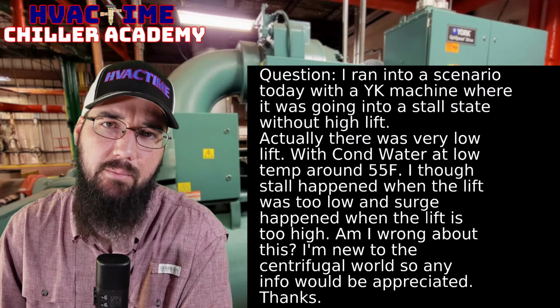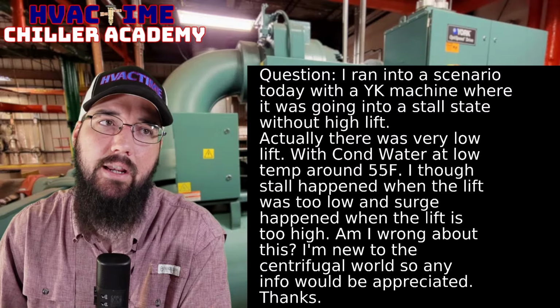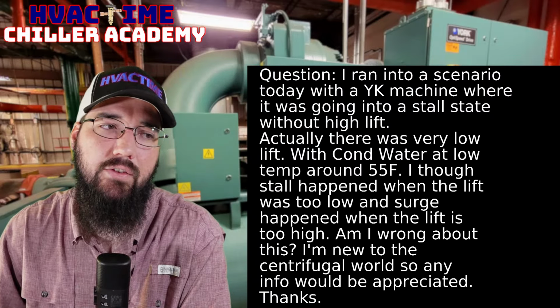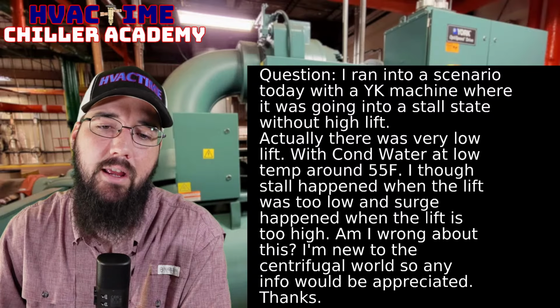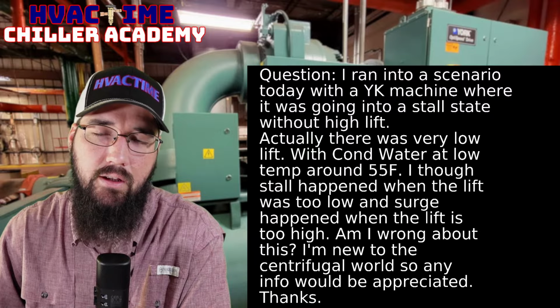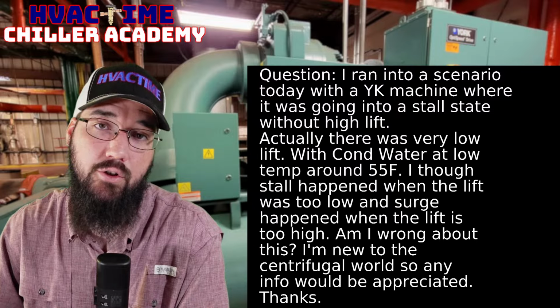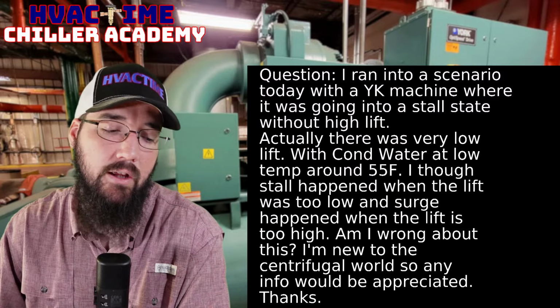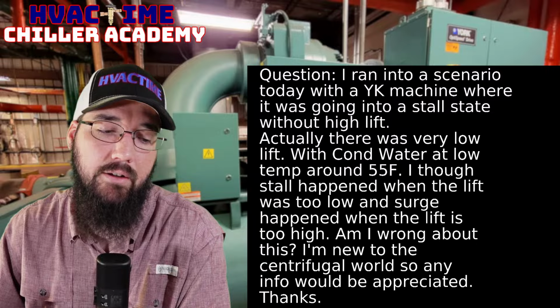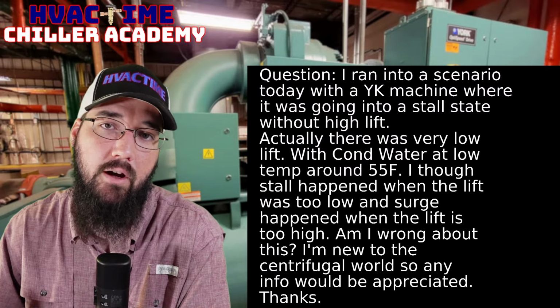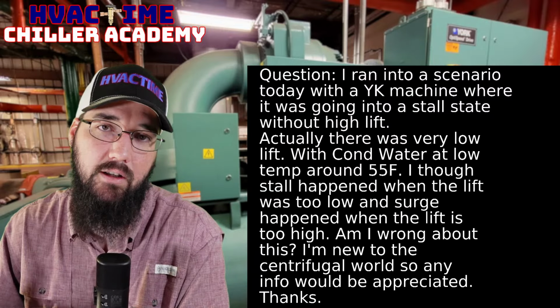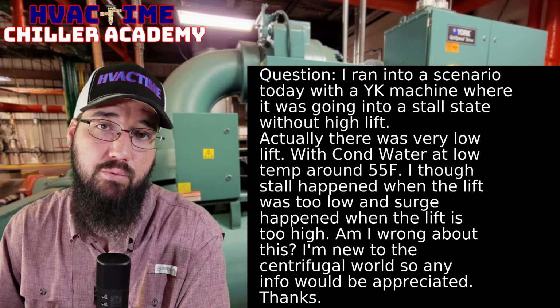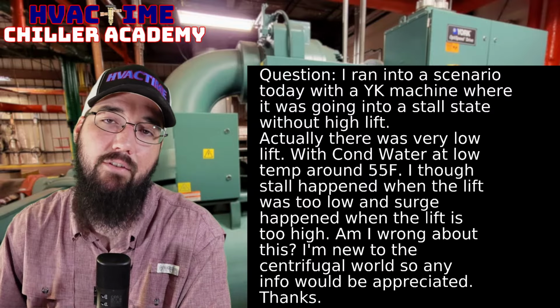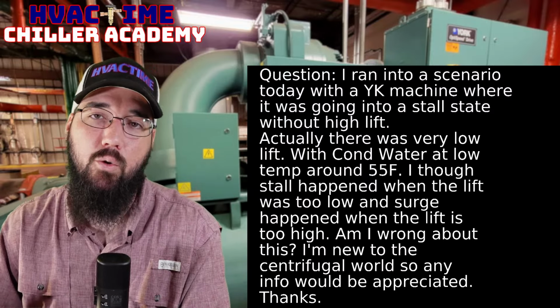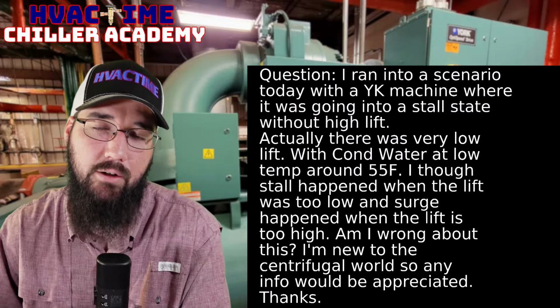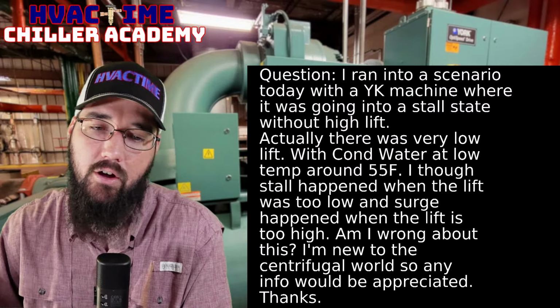But here's something to keep in mind with this. Trane has a similar thing where we have to maintain a minimum lift in order to, one, avoid choke. Now, if you read through Trane's literature, Trane explains that they're more concerned about oil flow control, because if our lift gets too low, it means our differential pressure drops too much, and we start having oil flow or oil management issues within the machine, and we'll start stacking oil in the evaporator and then cause all kinds of other problems.